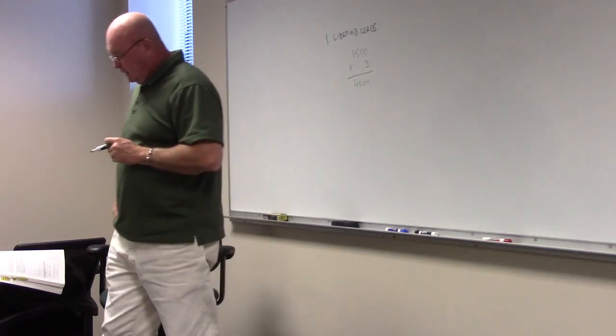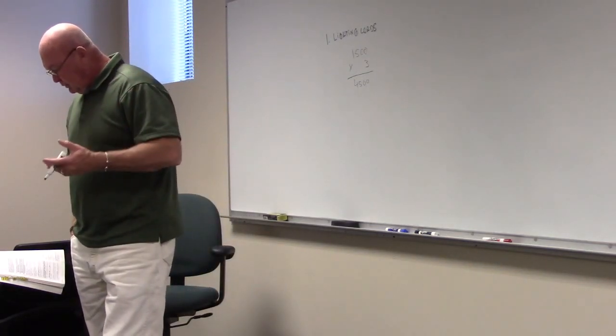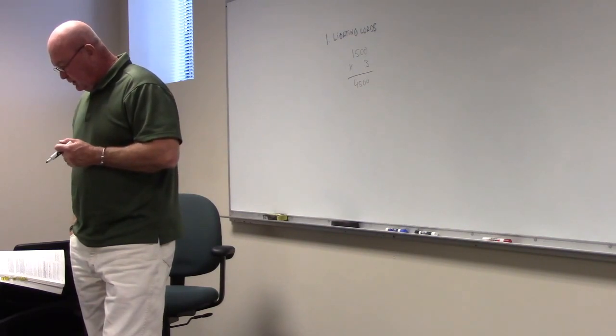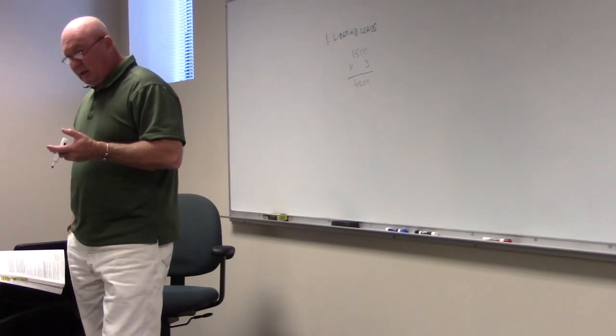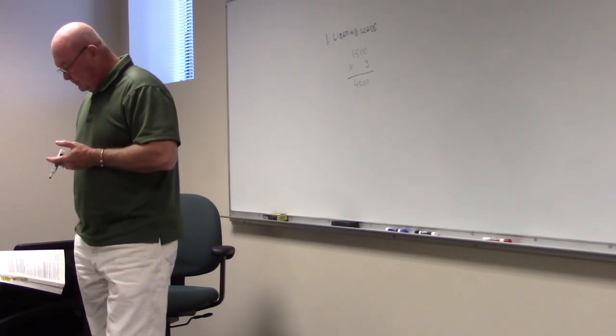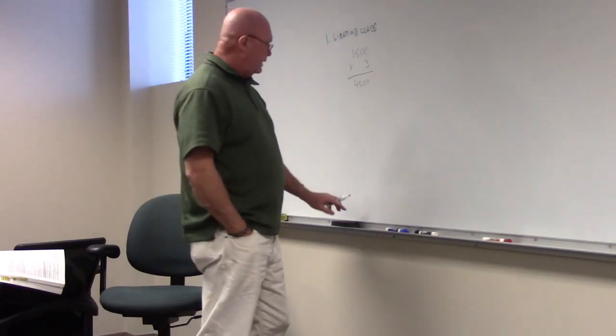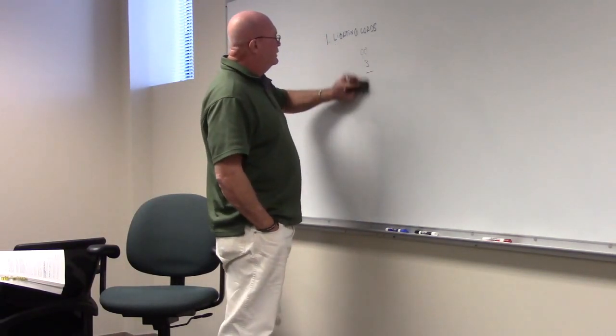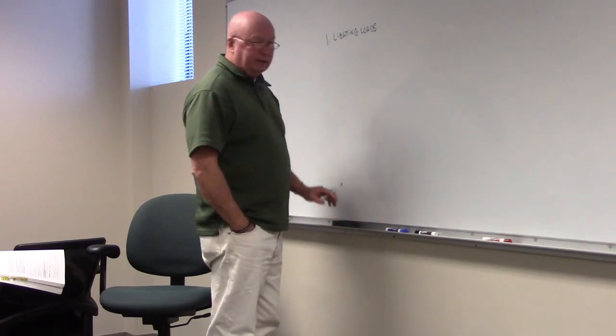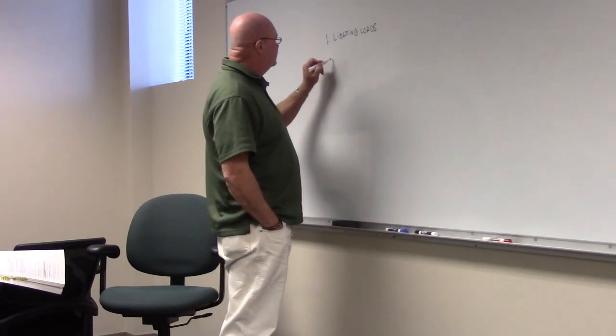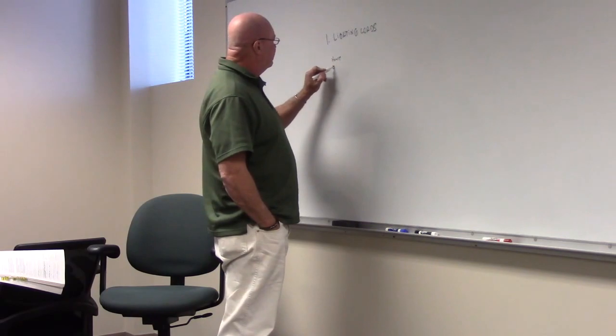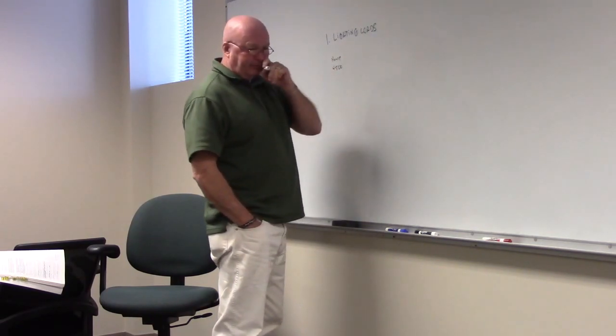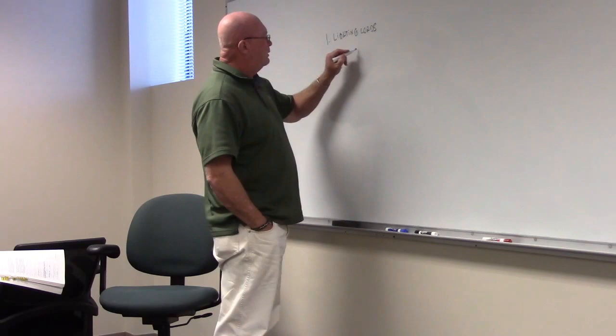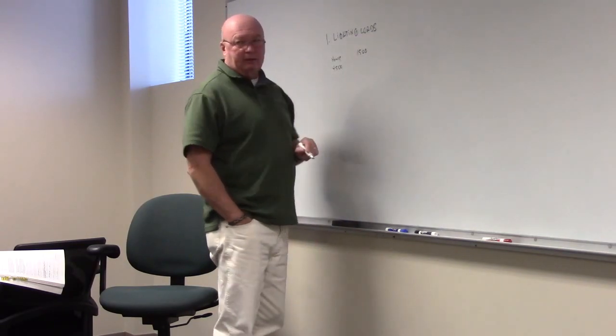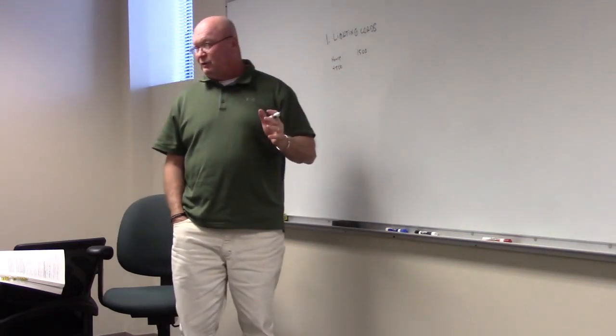If you read here, compute the floor area of the building using the outside dimensions of the building. This area is listed to determine the general lighting load for a particular occupancy. So each one varies. Let's look at a warehouse. We had 4,500 VA for a house. Let's say, for the sake of doing it, I know we wouldn't have one this small, a warehouse that was 1,500 square foot. What's your lighting load?